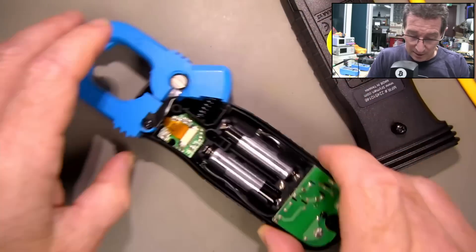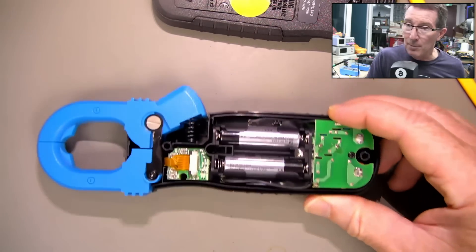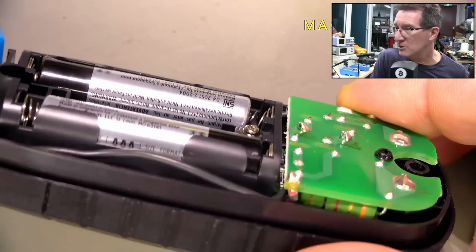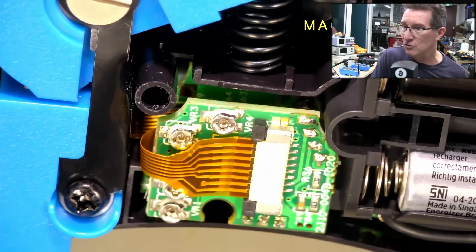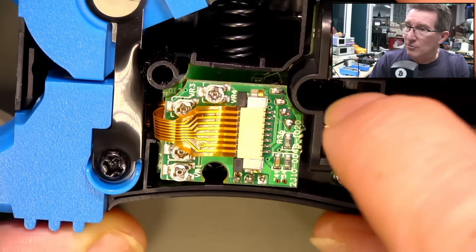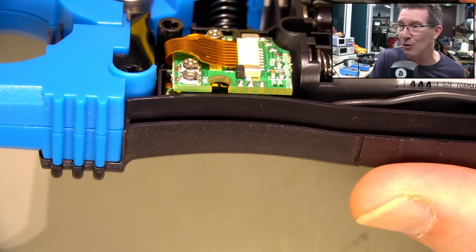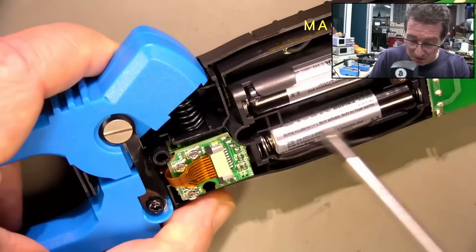Let's open this up and have a squiz. I assume it's not a battery-related issue because we're not getting a low battery warning. By the way, this company bought three of these — two of them have worked fine. I don't expect anything on the front board because it works hunky-dory. There are multiple trim pots in there. Brymen do not release schematics at all, so I don't have schematics or calibration procedures — I'm basically shooting in the dark, just looking for anything obvious.